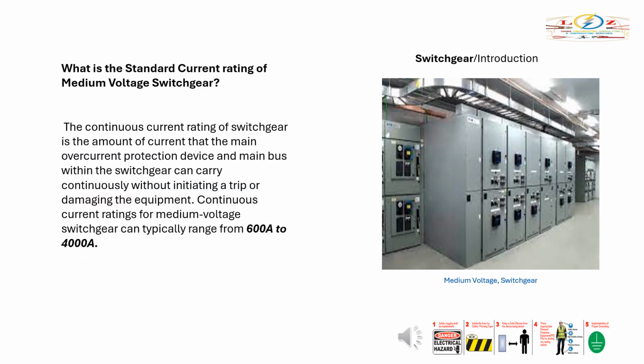What is the standard current rating of medium voltage switchgear? The continuous current rating of switchgear is the amount of current that the main overcurrent protection device and main bus within the switchgear can carry continuously without initiating a trip or damaging the equipment. Continuous current ratings for medium voltage switchgear can typically range from 600 amperes to 4,000 amperes.